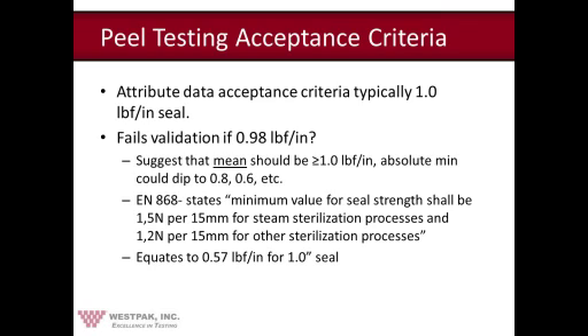And again, flexibility within your protocol is key. Do you have the ability to write into your protocol that the average seal strength for all samples is greater than 1 pound force, and an individual seal can dip below that as long as it stays above a minimum threshold, like 0.7 or 0.8 pounds?